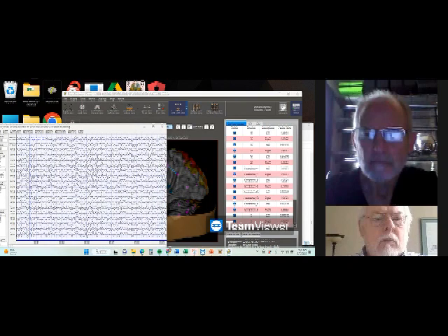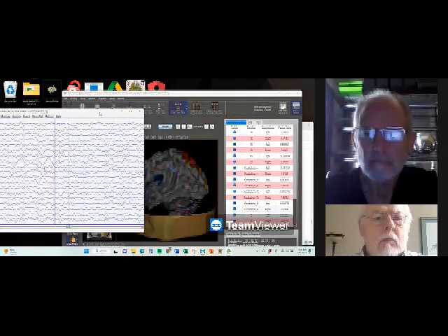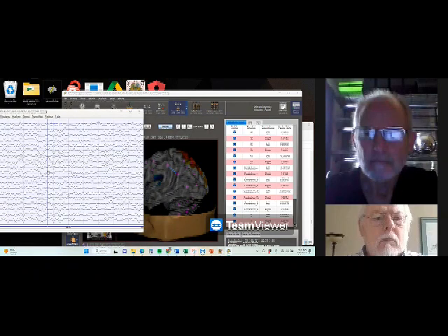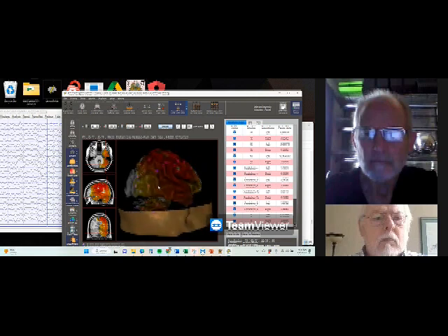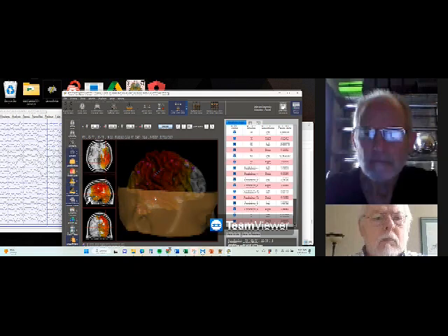So now you can just march through these. I can change the time scale. So I can go through the record. And so, as I mentioned, it's good for specific instances of time and for events that are not normal. So you can localize where the abnormal event happened.